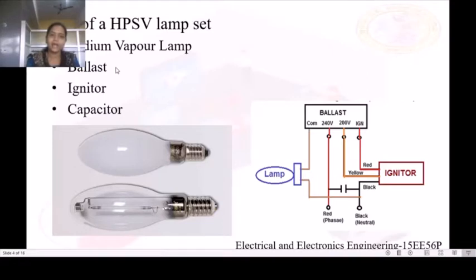Next, we have a ballast, choke or leak transformer. This ballast has got 4 terminals: common, 240 volt, 200 volt and igniter. Here the function of the ballast is to provide the ignition voltage that is required during starting of the gas discharge. That is, this high voltage is required to initiate the gas discharge inside the sodium vapor lamp. And also this ballast or leak transformer limits the current once the sodium vapor lamp starts conducting.